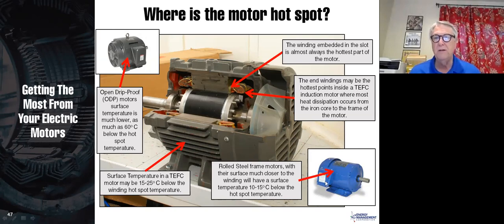On a rolled steel frame motor, that frame is in good contact with the outer steel frame. You have very quick thermal movement of the energy to the outside. And typically, these types of motors will have a surface temperature that's 10 to 15 degrees below the hotspot temperature. So if you measure the temperature on the frame of that motor, and then you add 15 degrees, that's a pretty good indication of how hot the temperature is inside the motor.